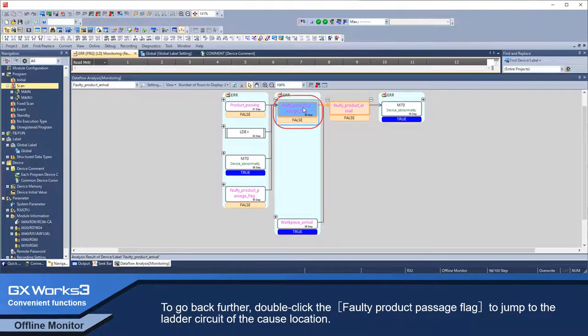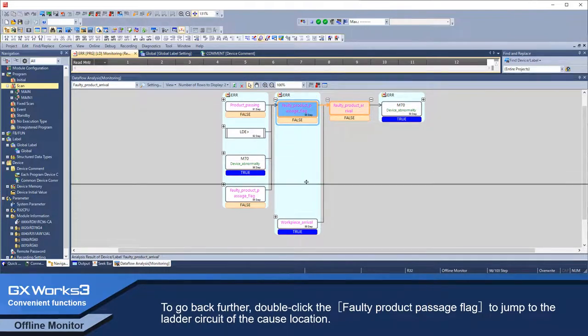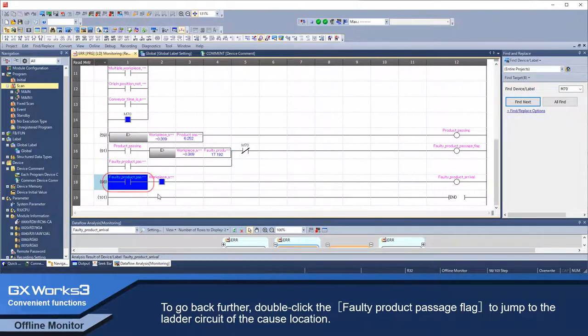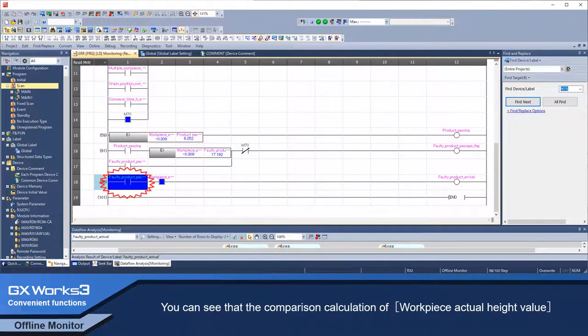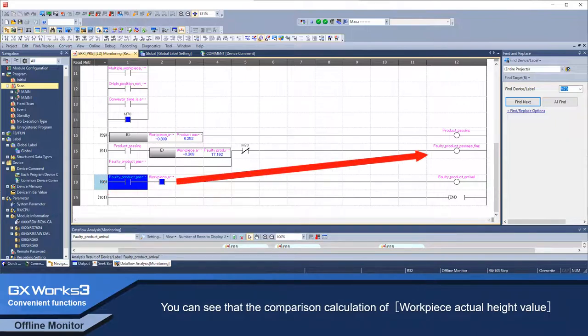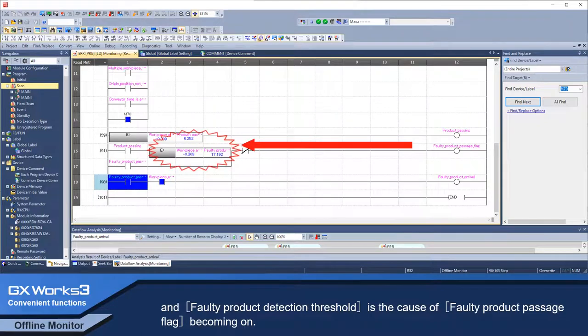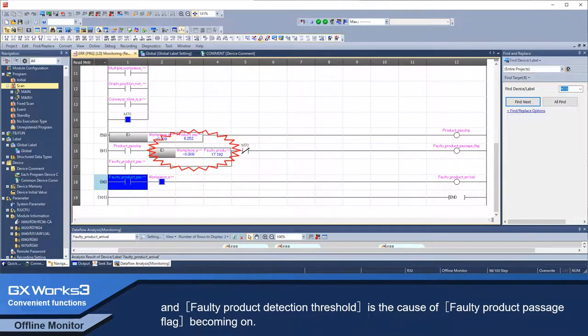To go back further, double-click the faulty product passage flag to jump to the ladder circuit of the cause location. You can see that the comparison calculation of workpiece actual height value and faulty product detection threshold is the cause of faulty product passage flag becoming ON.